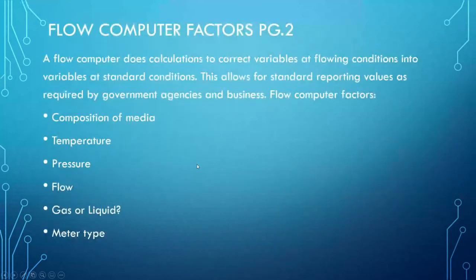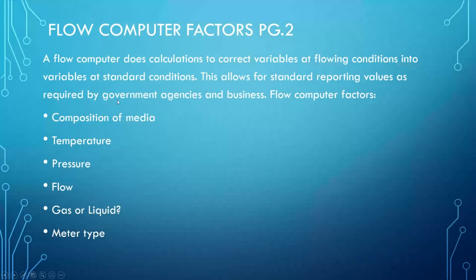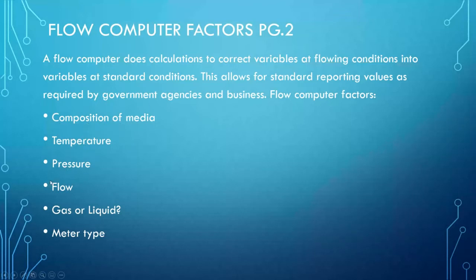The flow computer does calculations to correct variables at flowing conditions into variables at standard conditions. This allows for standard reporting required by government agencies and businesses that rely on exchange of goods and services. The variables involved include the composition of the media, the temperature, the pressure, the flow, whether it's a gas or liquid, and the type of meter being used.